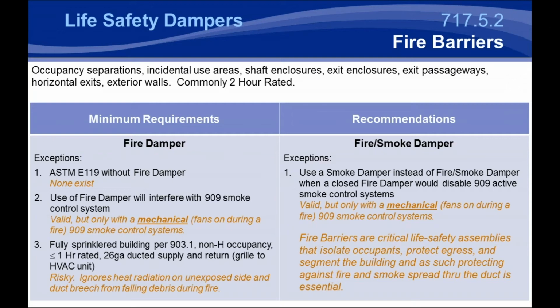One we'll get into is the third exception, where you've got a non-H rated occupancy that's fully sprinklered and has fully ducted supply and return systems. So there's no flex duct used, minimum of 26 gauge duct going through this fire barrier. And there's sprinklers. Now the problem with that and the added protection of a fire damper is there could be a duct breach. So imagine there's a fire and there's things degrading above that could potentially fall and hit and either puncture or rip this duct completely out of the wall.